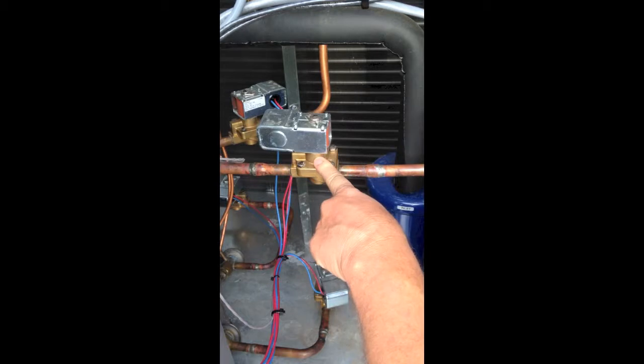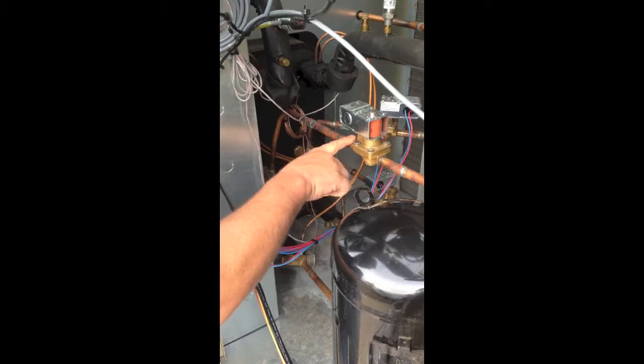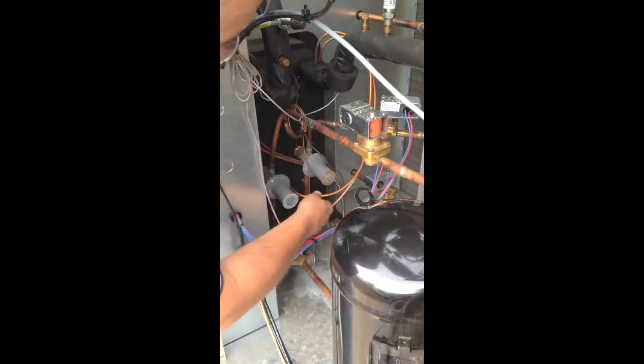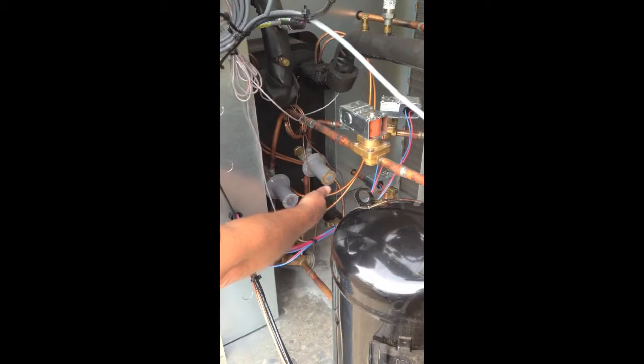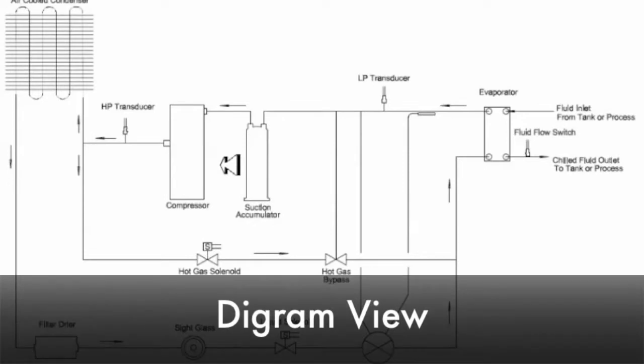Now, about 90 seconds after the compressor starts, this solenoid valve will open, allowing the hot gas to go to our regulator valve. All right, so when the hot gas goes through the solenoid valve, it proceeds down in here to a regulator valve. And this regulator valve is what makes the decision, if you will, to inject hot gas into the evaporator.